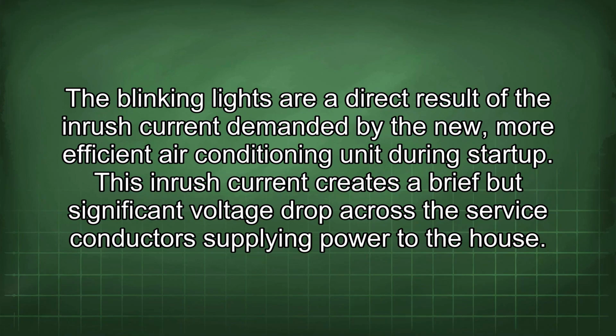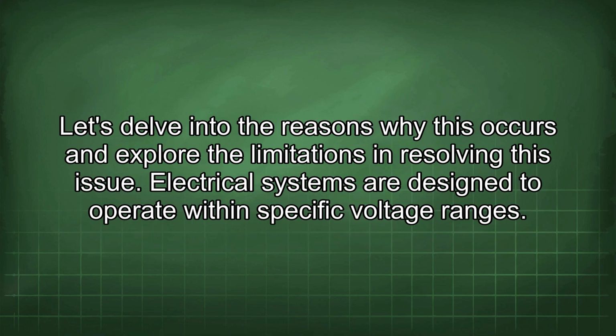The blinking lights are a direct result of the inrush current demanded by the new, more efficient air conditioning unit during startup. This inrush current creates a brief but significant voltage drop across the service conductors supplying power to the house. Let's delve into the reasons why this occurs and explore the limitations in resolving this issue.